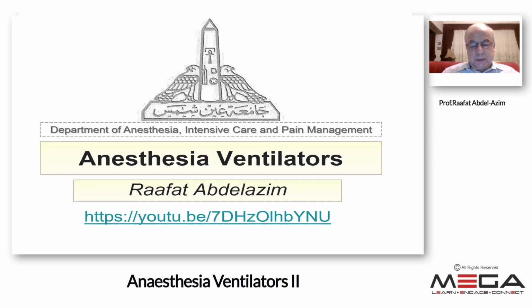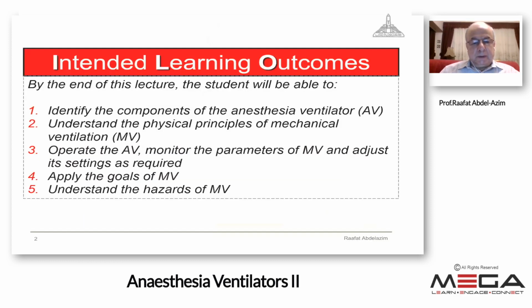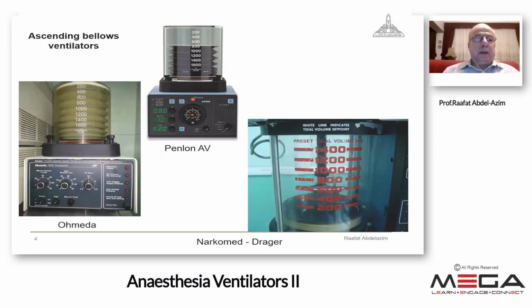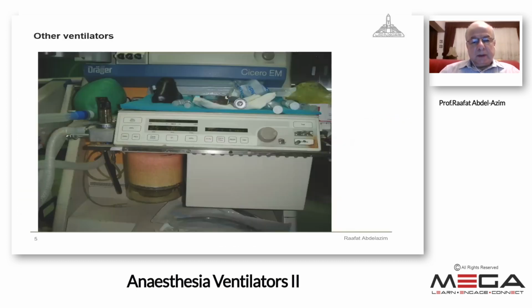In a few minutes, I will summarize what was given before to continue the topic without confusion. As you said, the anesthesia ventilator is a very important part of our practice. I categorized the ventilators into three categories. The first one, which is essential to understand first before going to the newer versions, is what we call traditional ventilators or ascending bellows ventilators. These are examples of the ascending bellows ventilators. In ascending bellows ventilators, we can see the bellows going up and down. Other ventilators are, for example, Draeger, and in other ventilators, we cannot see the bellows. There is a different mechanism for operating the ventilator.